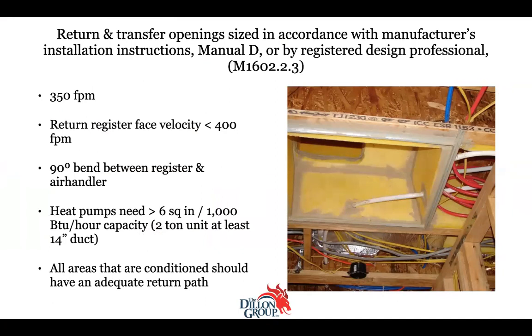You want the airflow going across the coil on the return side at about 350 feet per minute, which means you need to have a big return duct, a bigger return plenum than you have on the supply side. And the face velocity at the return register, you need it about 400 feet per minute or less. And you want a 90 degree bend in if you can get it, because it reduces the amount of noise. But for heat pumps, just as an idea, this is a good equation to use: they need to have at least 6 square inches per 1,000 BTUs per hour of capacity of return duct cross-sectional area. So again, on a 2-ton unit, you're talking about a 14-inch duct.